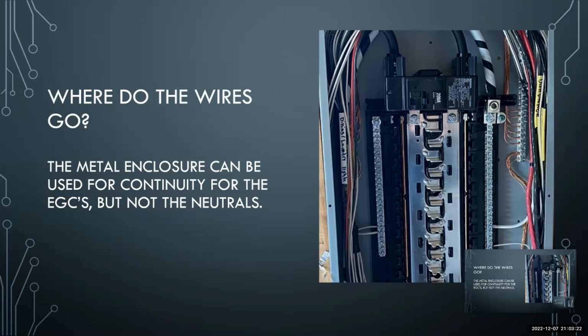Is there a way to know if it's making contact with the box? Well, you could ohm it out, but that's just a no-brainer to me. In a sub panel there's no purpose for it to be sitting there. Take it out, put it in your pocket, put it in your toolbox, and use it on the next service panel when you lose the bonding screw. It shouldn't even be in that sub panel.